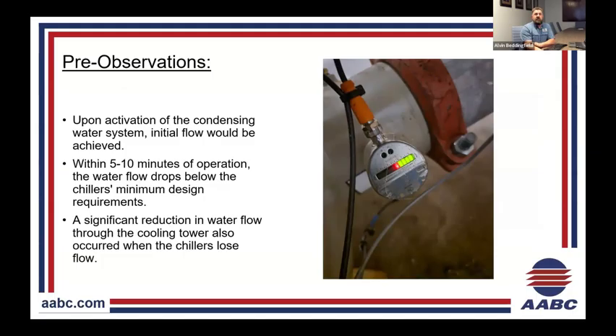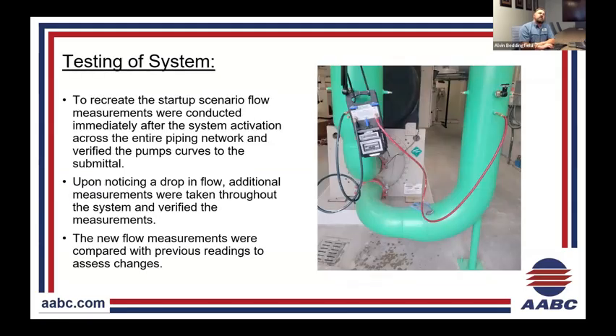The chiller would actually try to start, and then about 5 to 10 minutes after, flow would completely drop, and then we'd lose the chiller. Another observation while we completely lost the flow is that we noticed the condensing water going over the cooling tower was significantly reduced, so we knew we had some sort of water shortage coming through the system. So we decided to retest it and try to figure out what we were seeing.